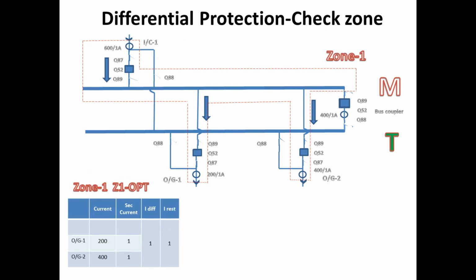Actually this is a maloperation, this is not an actual fault. To avoid this, we go for check zone. What is a check zone? Check zone will check all the CTs except the bus coupler.